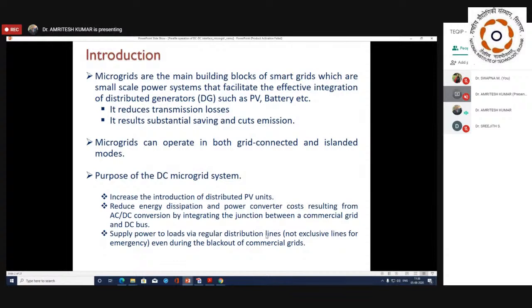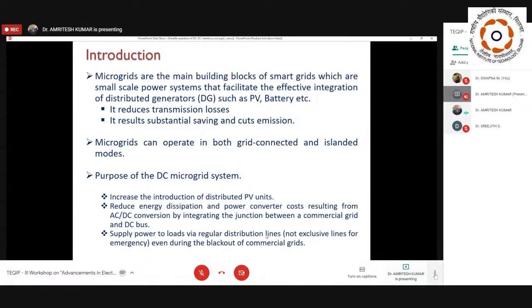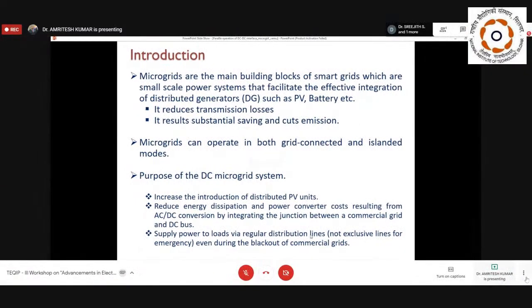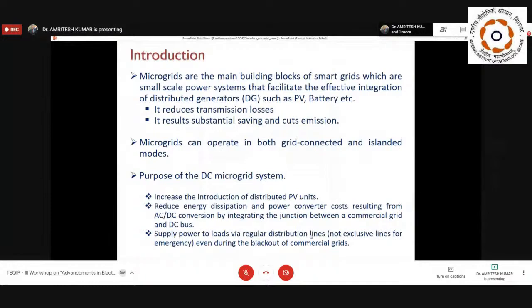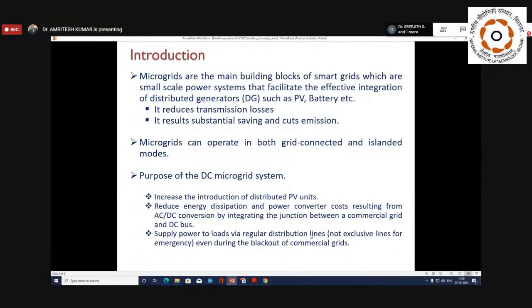So if we take the power from the AC grid, we require converters, first AC to DC, and thereafter again you need to step up or step down. So there are going to be a number of cascaded converters, and each converter is going to have some efficiency. Even if I take 0.9, there are going to be losses in the conversion process. If we use a DC microgrid, the losses from multiple conversions can be minimized. That is a major benefit of the DC microgrid.